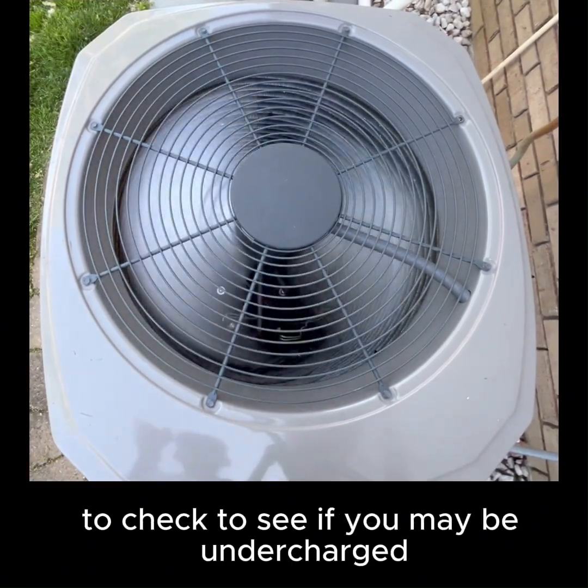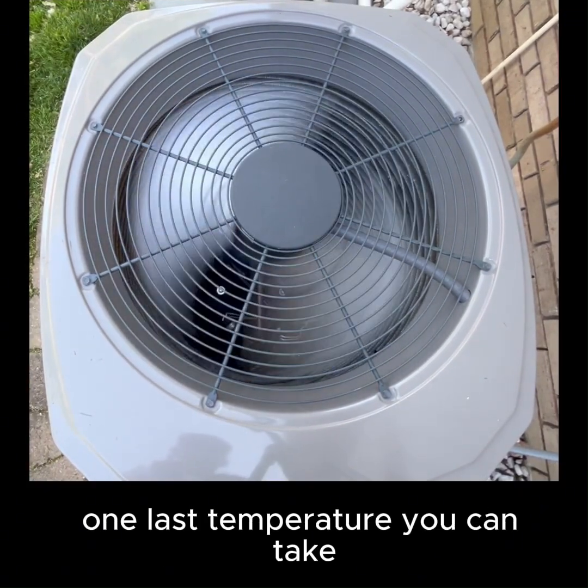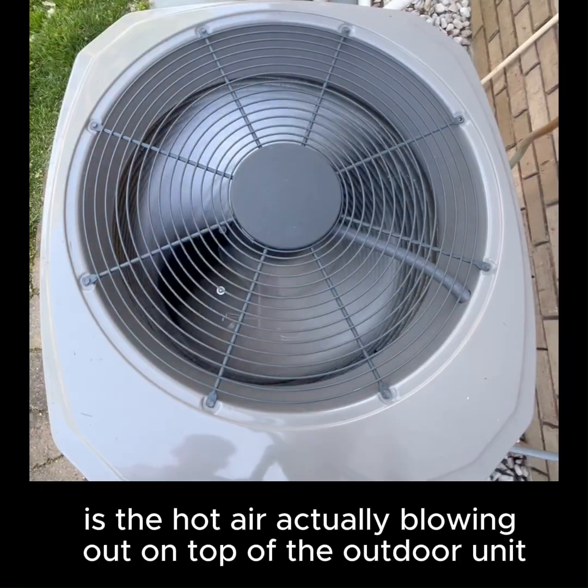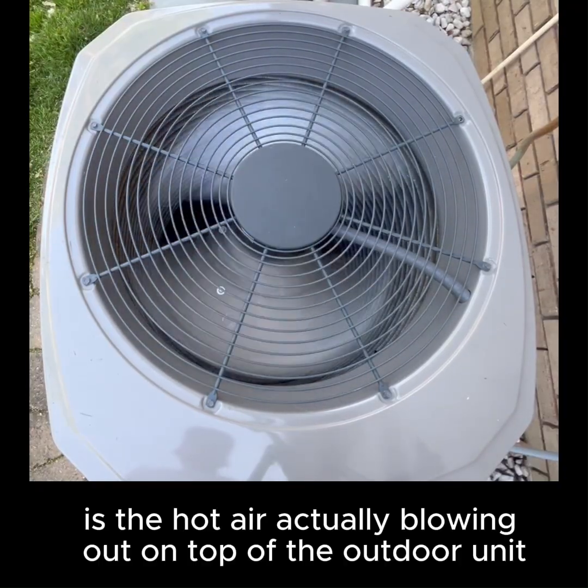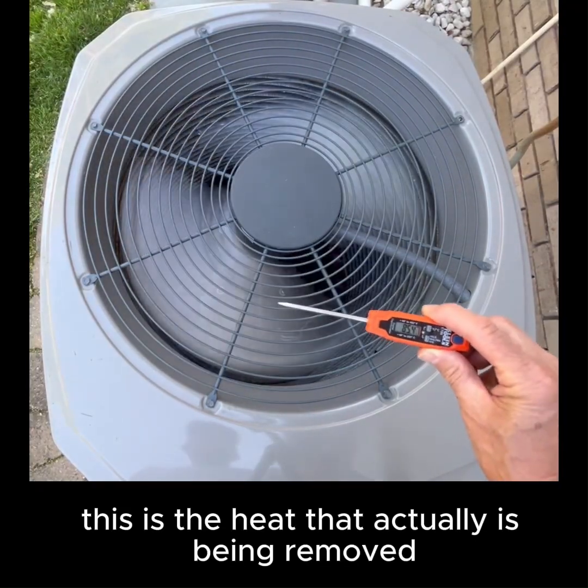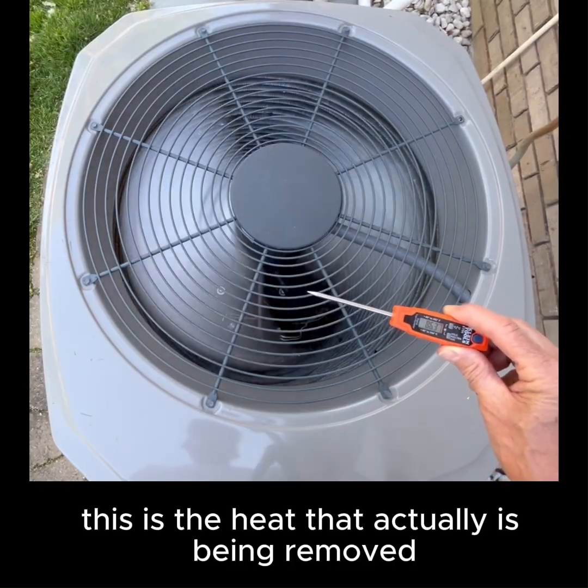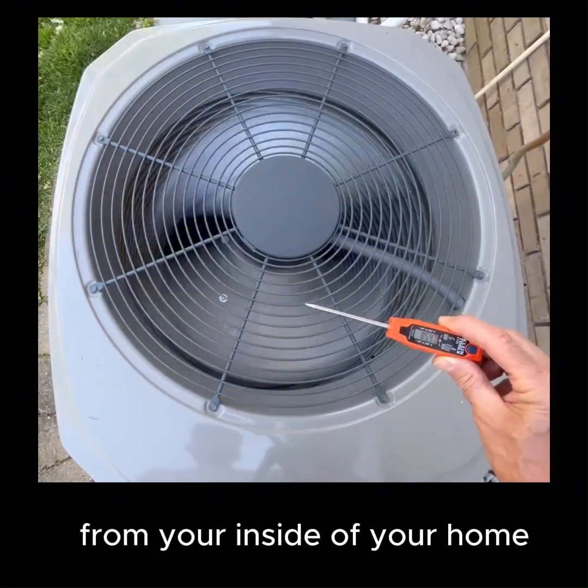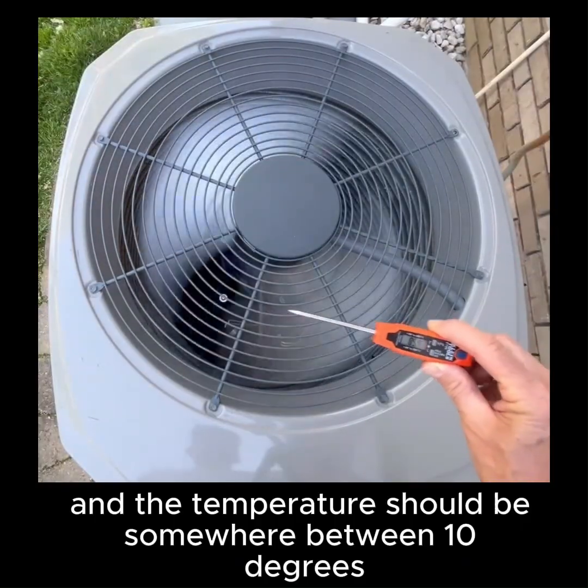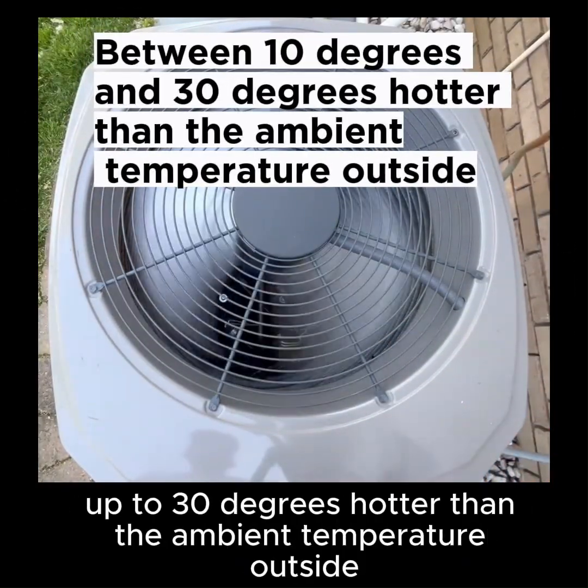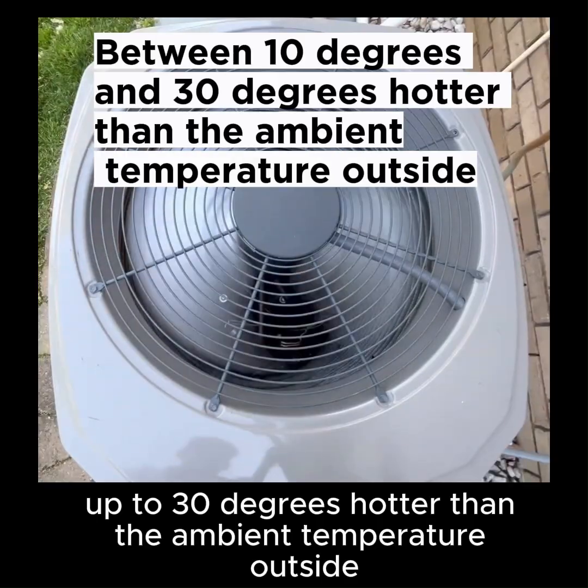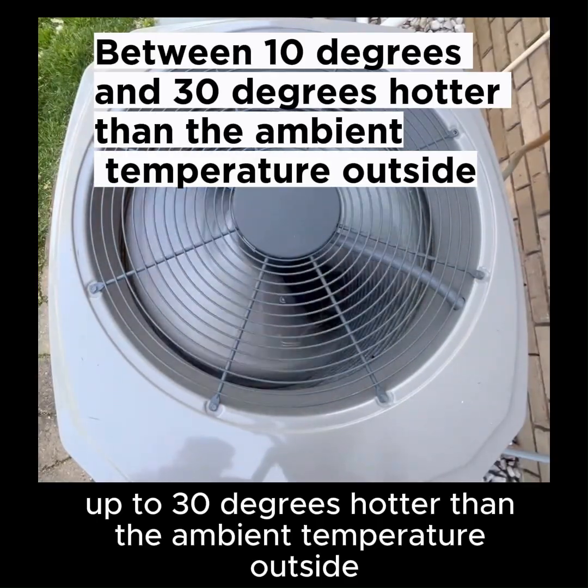To check to see if you may be undercharged, one last temperature you can take is the hot air actually blowing out on top of the outdoor unit. This is the heat that actually is being removed from the inside of your home. And the temperature should be somewhere between 10 degrees up to 30 degrees hotter than the ambient temperature outside.